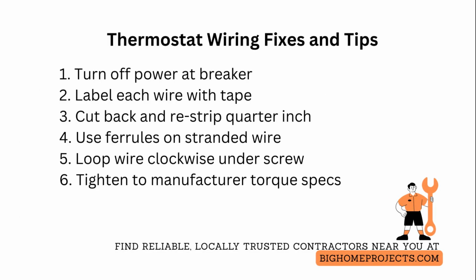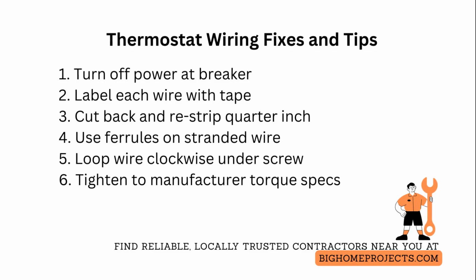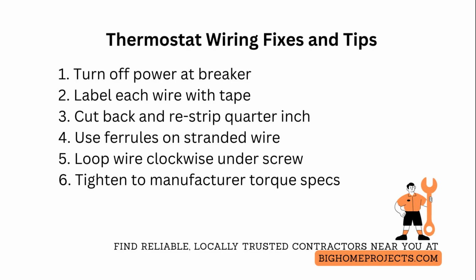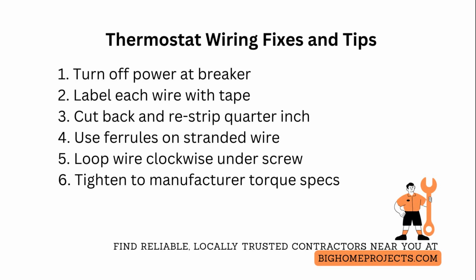For a reliable repair, start by turning off power at the breaker and labeling each wire with small tape so you never swap zones. Then remove the thermostat cover and gently pull the base away to expose the terminal block while keeping track of the wall plate orientation.